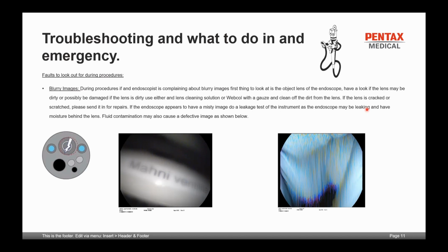So having a look at blurry images, during the procedures, the endoscopist might complain about a blurry image. So your first standpoint to look at would obviously be the objective lens of the endoscope. If you have a look at the objective lens, it might be dirty or possibly damaged. If the lens is dirty, you could use a lens cleaning solution with a gauze or a swab and clean the dirt off the lens and then recheck the image to see if it has cleared up. If the lens is cracked or scratched, it will unfortunately have to go in for repairs, but you would be able to identify that on site.